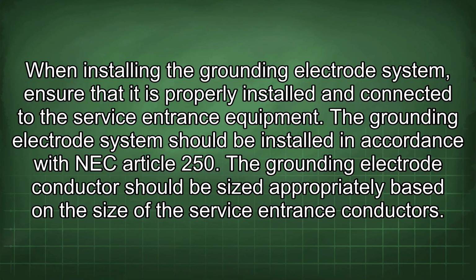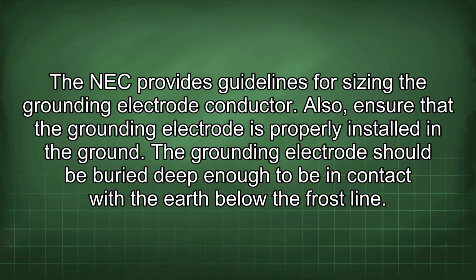When installing the grounding electrode system, ensure that it is properly installed and connected to the service entrance equipment. The grounding electrode system should be installed in accordance with NEC Article 250. The grounding electrode conductor should be sized appropriately based on the size of the service entrance conductors. The NEC provides guidelines for sizing the grounding electrode conductor.